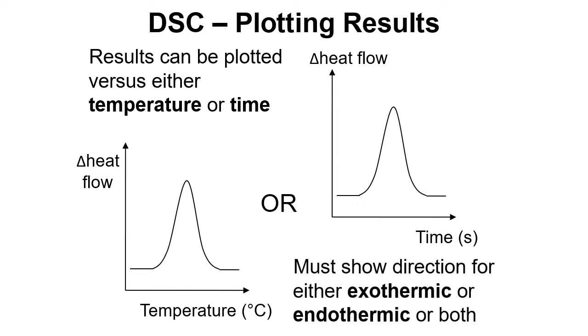What's important is that we must show the direction for either an exothermic event or endothermic event or both. We need an arrow somewhere on the thermogram showing us which direction is exothermic or endothermic, or arrows for both of them. That's because there's no convention over which way is exothermic and which way is endothermic, and so we need to indicate that on our thermograms.